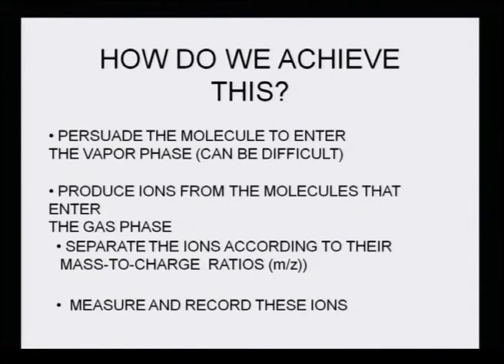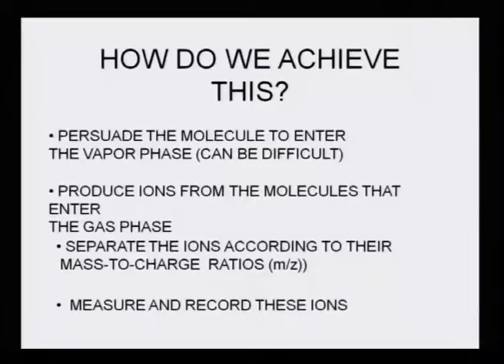There is an ion source which bombards the molecule, then an analyzer which analyzes the different fragments according to their m/z ratio, and then a detector. Separating ions according to their m/z and measuring and recording these ions are the four main functions that happen in a mass spectrometer.